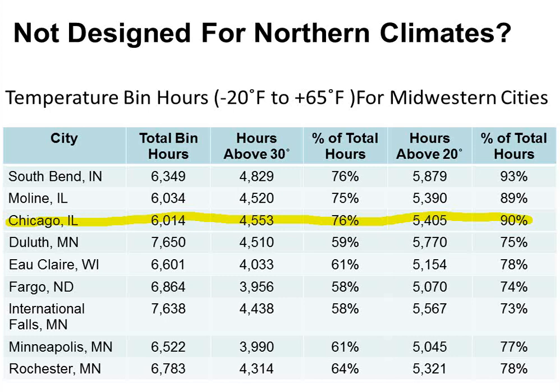In a commercial building, if you look at the ASHRAE handbook, you don't want to be any more than 15 degrees above the space temperature. So if your space temperature is, say, 75 degrees, you don't want to be any more than 90 degree discharge temperature, because it's going to cause the air to stay stratified up at the ceiling and not do a good job of mixing down into the space, and you short cycle your air. And technically you have to take an outside air calculation penalty and provide 25% more outside air requirements than you normally would. It causes a whole big mess.